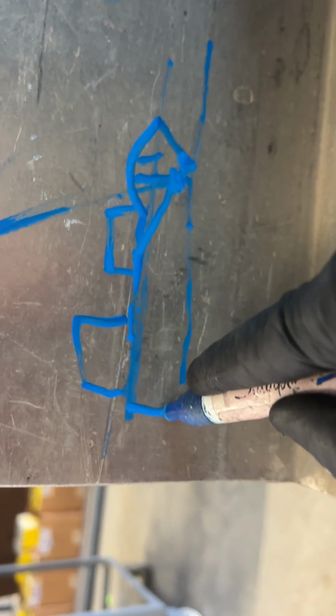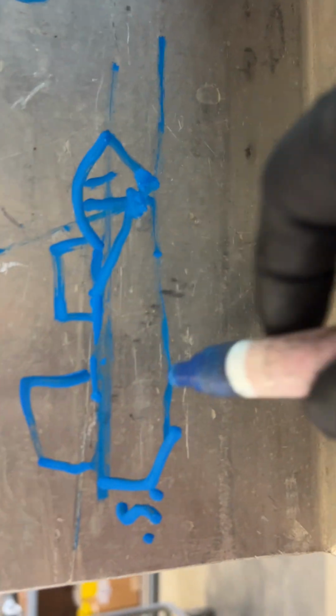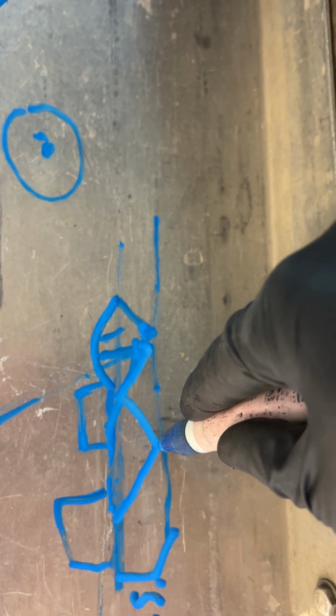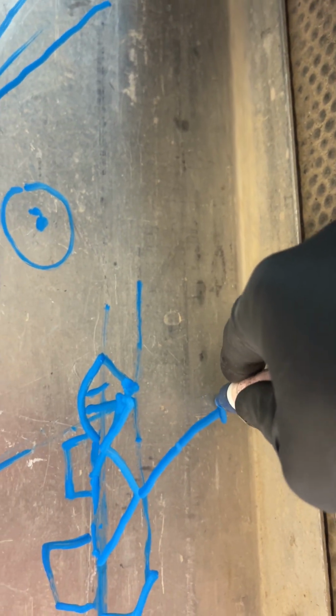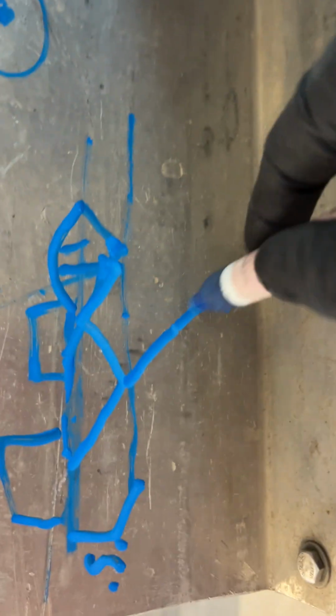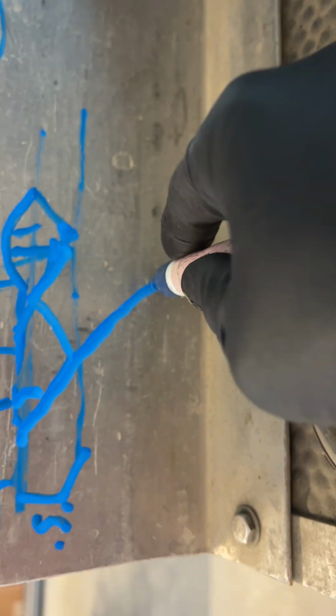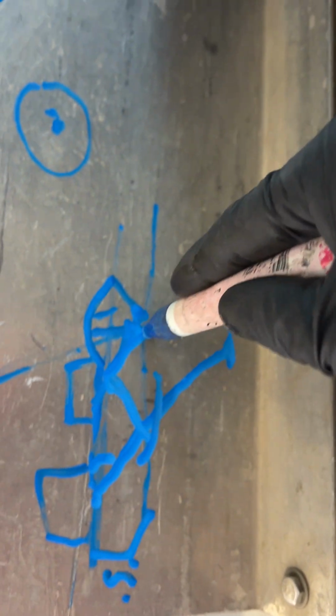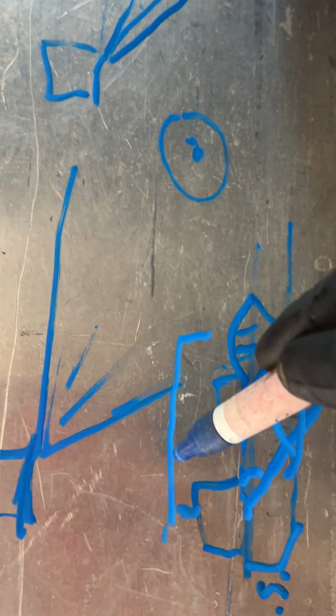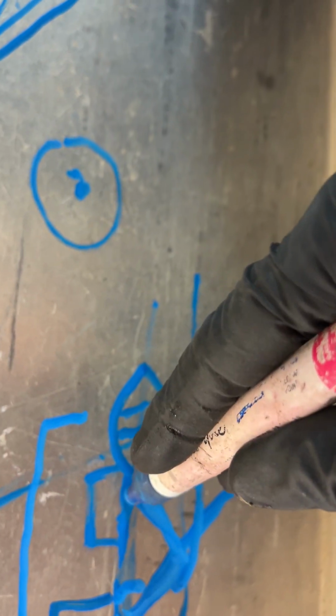This is what the trig will do. You tell it this is 0.5 of an inch. You put it in right there, and it's going to figure it out. You shoot from here, it's going to go 1, 2, 3 to find the same thing. It doesn't fucking care. It's going to go 2, 3, and it says it's way down here. But the trigonometry is automatic. It knows 69.8 degrees and the sound path and the thickness. So it just mathematically bounces out. And it'll tell you from your index point how far out you're going and how far down it is. Because it knows that it went a full depth, you're back at 0. And this one, it went 3/4. It knows you're 3/4 of 0.5. It'll figure it out.